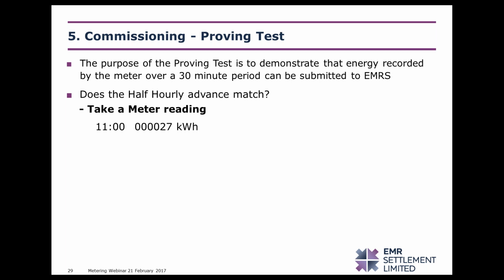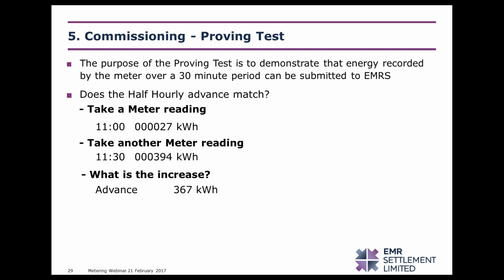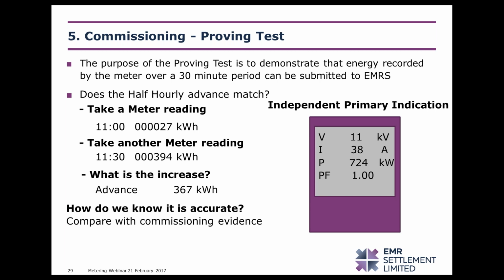If you were to take a meter reading, you would take it at the start of a half-hour period. So in this example, a reading was taken at 11 AM and the cumulative energy register was reading 27 kilowatt hours. You have to take a second reading at the end of that half-hour period, in this case 11:30, and the cumulative energy register has advanced to 394 kilowatt hours. The half-hourly advance is the difference between those two readings, and in this case is 367 kilowatt hours. One of the reasons that we recommend doing the commissioning at the same time as this proving test has been carried out is so that there can be a comparison with the prevailing load evidenced in the commissioning test results to validate that half-hourly advance.